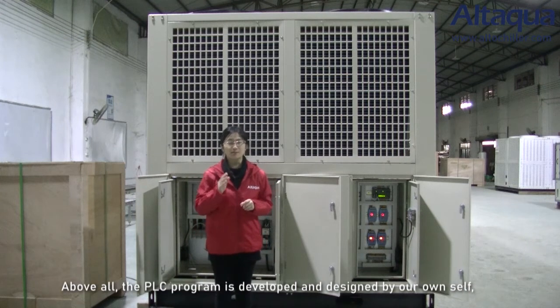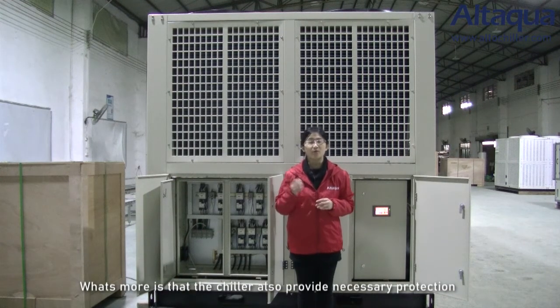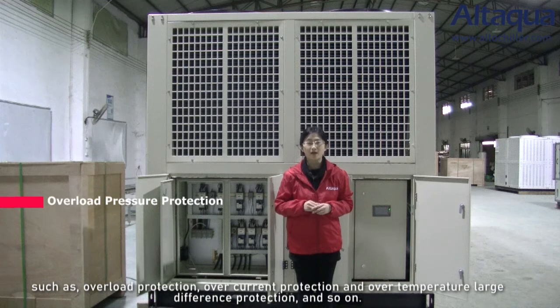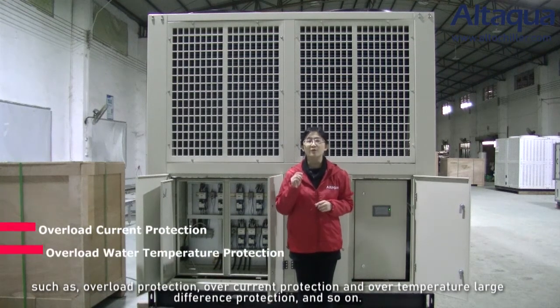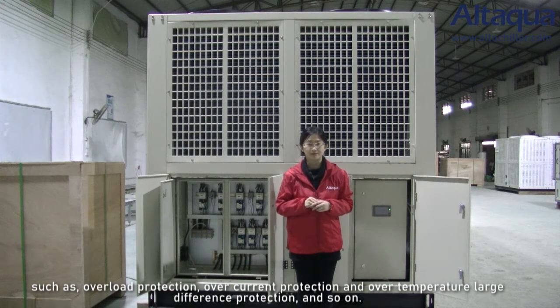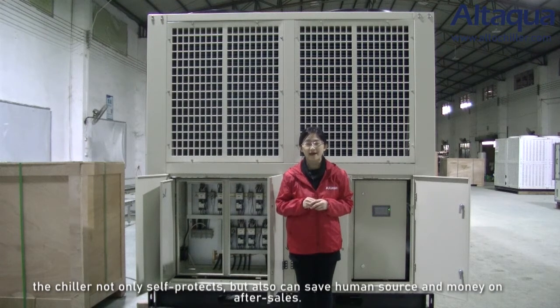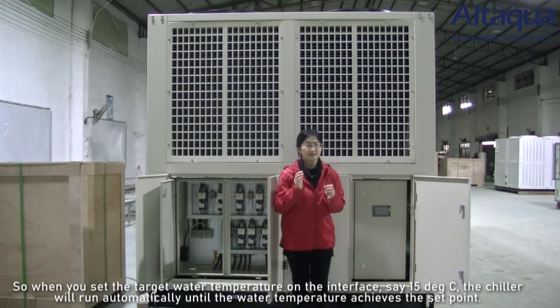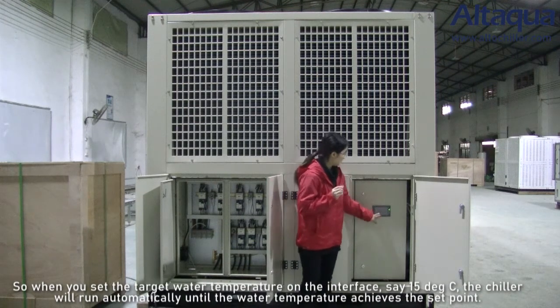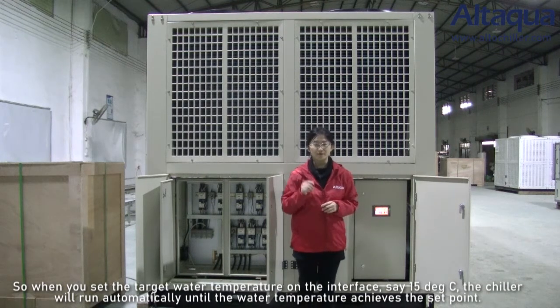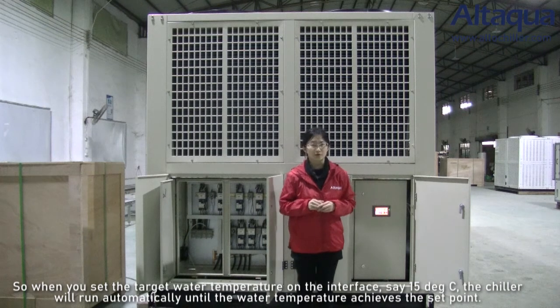Above all, the PLC program is developed and designed by ourselves. What's more, the chiller provides many necessary protections, such as overload protection, overcurrent protection, and over temperature large difference protection, and so on. It means the chiller not only can protect itself, but also can save so much human resource and money on after sales. So when you set the target water temperature on the interface, say for example 15 degrees centigrade, the chiller will run automatically until the water temperature achieves the set point.